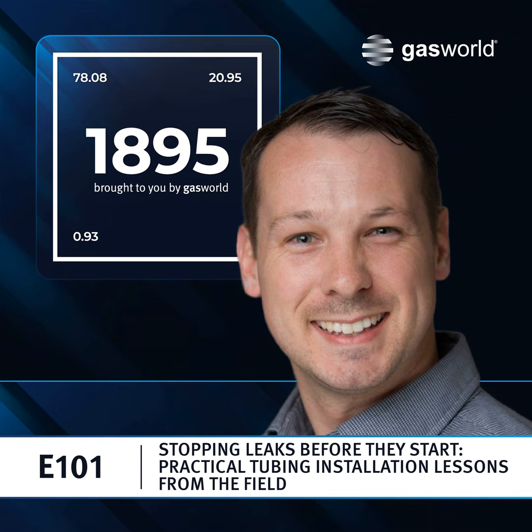Yeah, a lot of people think that many of the issues come from the product, but like you hinted at, I think a lot of the root causes that we see with leaks or failed fittings really come from the challenges in installation. So many of the things that we see, probably first and foremost, is either improper tightening, so typically either under tightening or over tightening the fitting. Before that, you can have issues with tube preparation, tube bottoming in the fitting. Those are kind of some common installation issues.